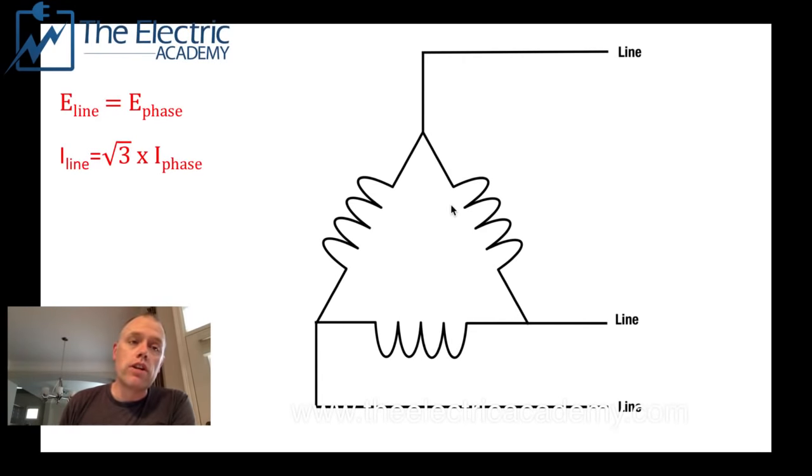Some motors, just as a note, they'll have these soft starters. So they're going to start a motor. They'll start it in Y, and then they'll move it up to delta because you've got a lower current in Y and a higher current in delta. So they call them soft starts, a Y delta soft starter. Again, maybe I'll do a video on Y delta soft starters later on in the year here.